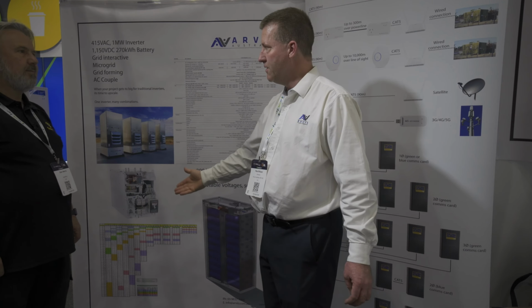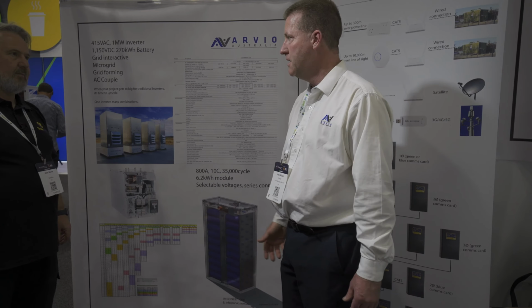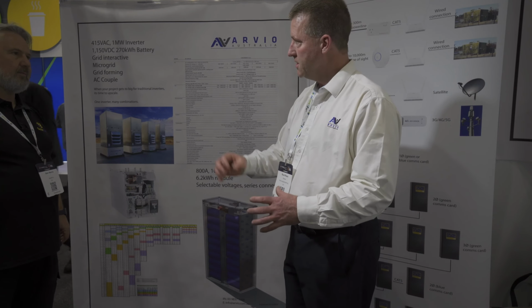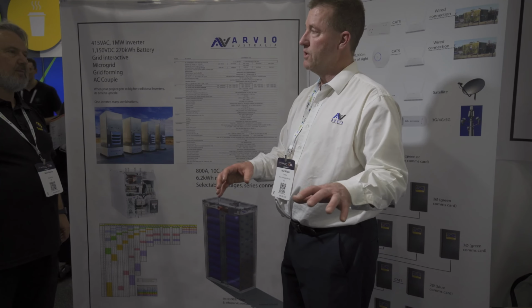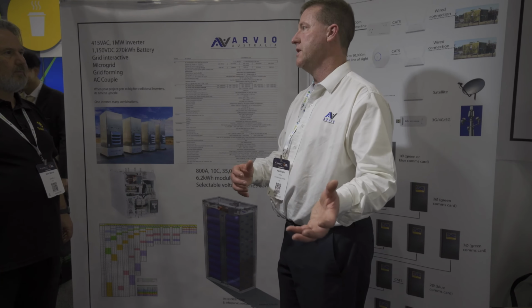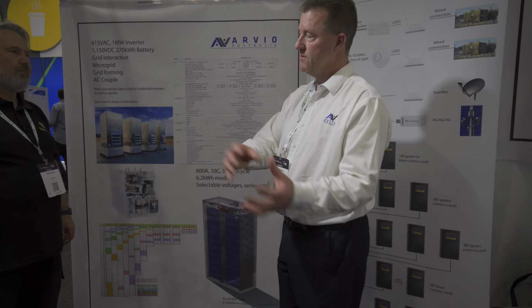So you can put Fronius on the load side, for example, or some other brand, and then we can pull that power in and charge and discharge the battery. We can interact with the grid, and if the grid fails, we can open circuit and grid form. When the grid recovers, it can reconnect.